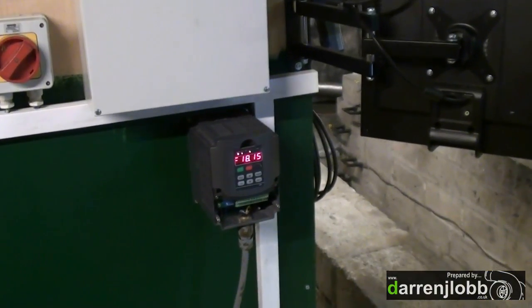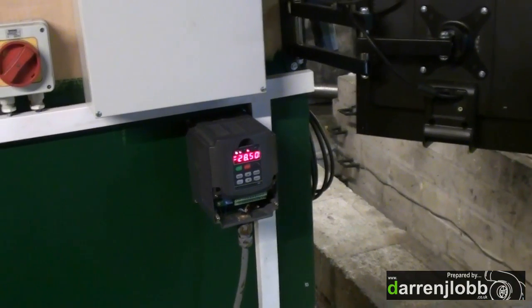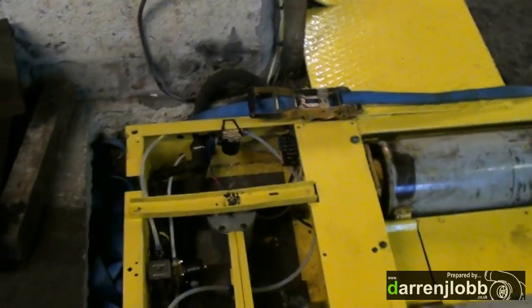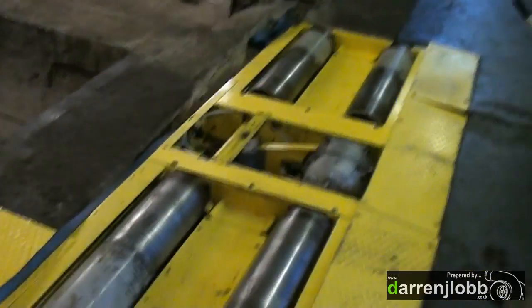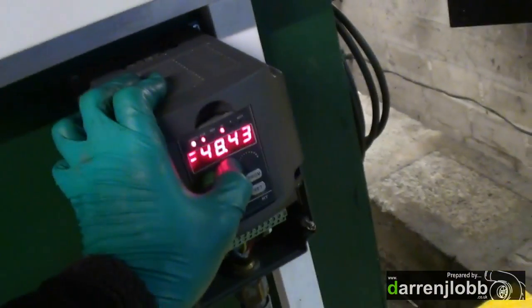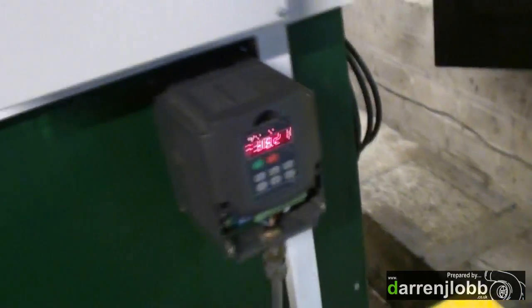That'll just ramp up the water pump - you can hear some air splashing into the tank. So it's now pumping water through the heat exchangers and back through the returns, and we actually didn't have very many leaks - just a couple of small ones that wanted their jubilee clips tightening down. Other than that, the water side is working. You just press stop again and it ramps back down.